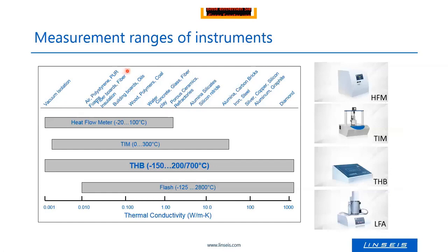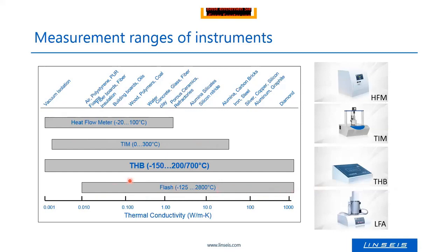The next slide shows the measurement ranges for individual instruments. You can see the heat flow meters — the steady-state instruments — are for lower conductivities. The TIM tester, also a steady-state method, can measure somewhat higher conductivities. The laser flash has a very broad range up to very high conductivities. And the THB has most probably the broadest thermal conductivity range — it can measure more or less all kinds of samples in the temperature range between minus 150 and 700 degrees Celsius.